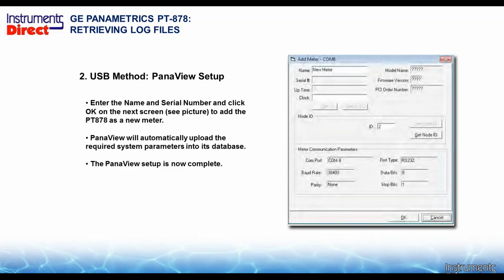So here, we need to enter the name and the serial number and click OK on the next screen. The serial number you'll find on the back of the flow meter. See the picture to add the PT878 as a new meter. PanaView will automatically upload the required system parameters into its database. And the PanaView setup is now complete.